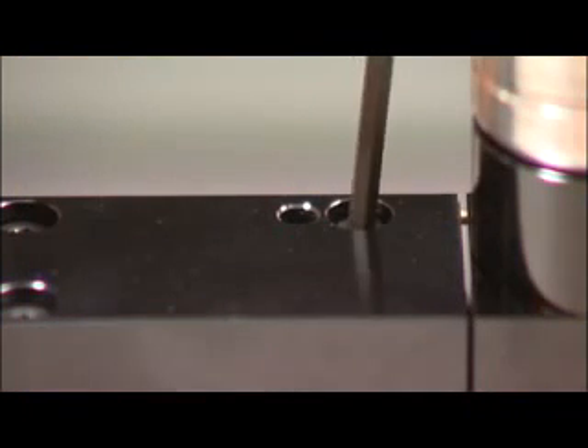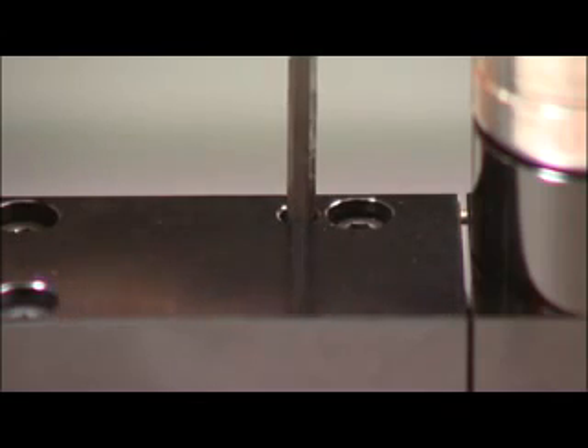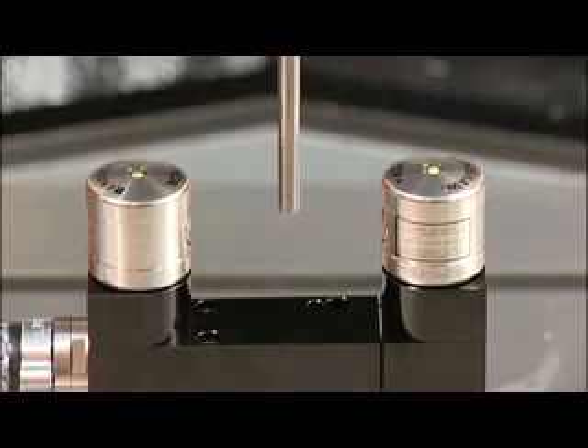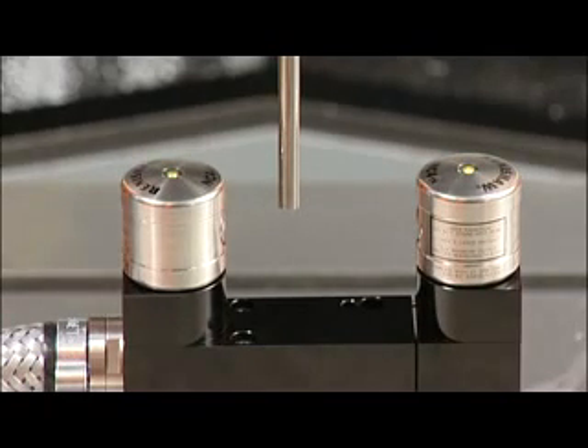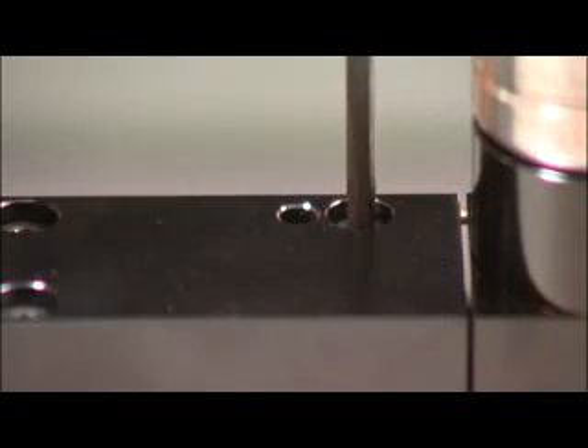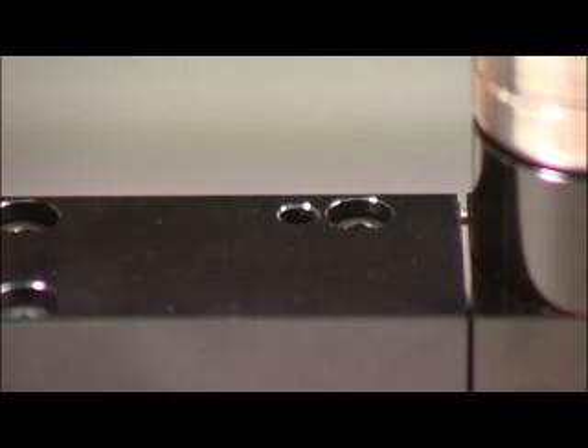Slacken the Z-axis locking screw. Adjust the Z-axis adjusting screw. Check the beam alignment. This can be an iterative process. Carefully tighten the Z-axis locking screw, taking care not to move the NC4 fixed unit.